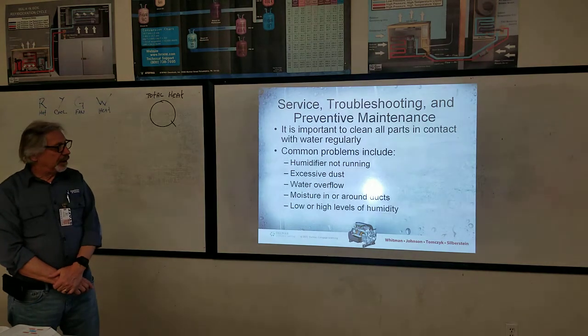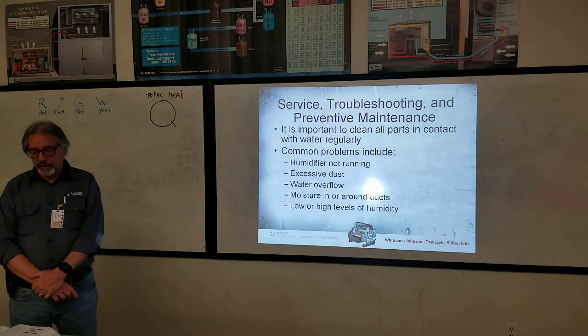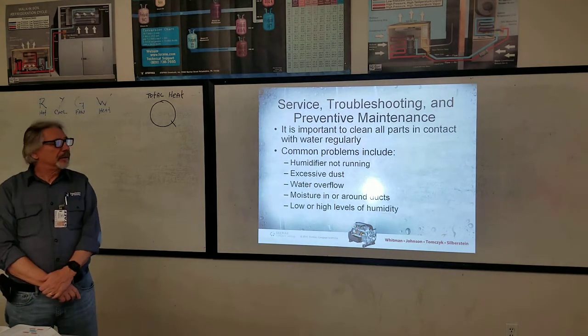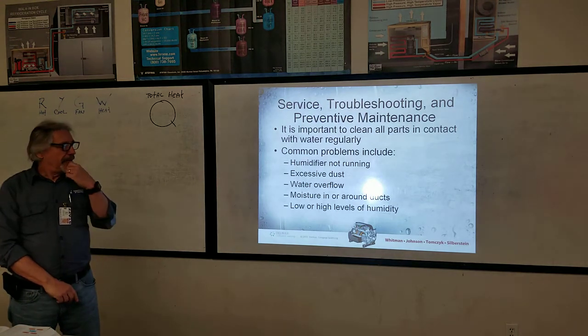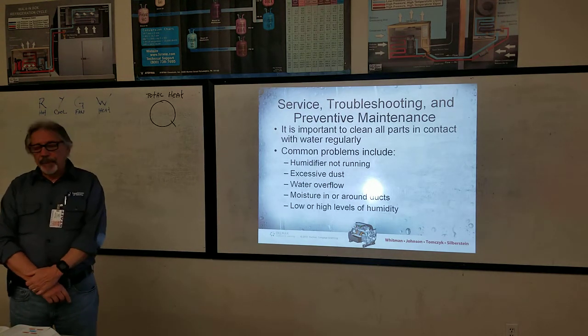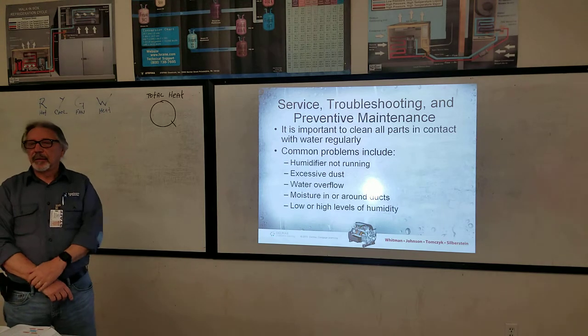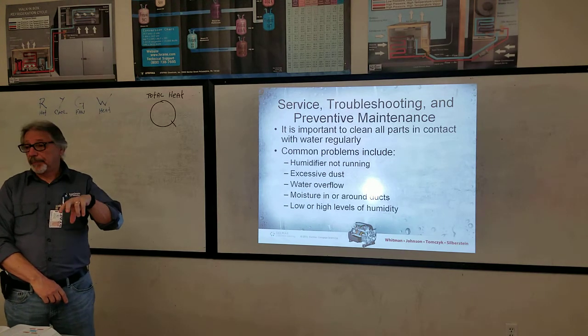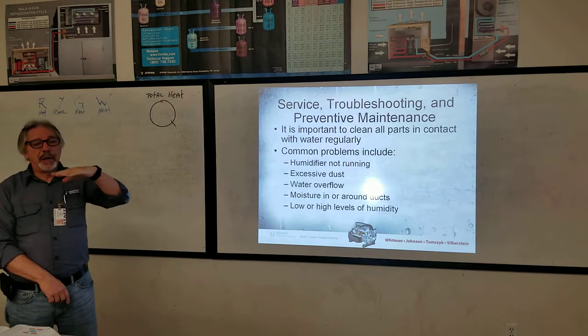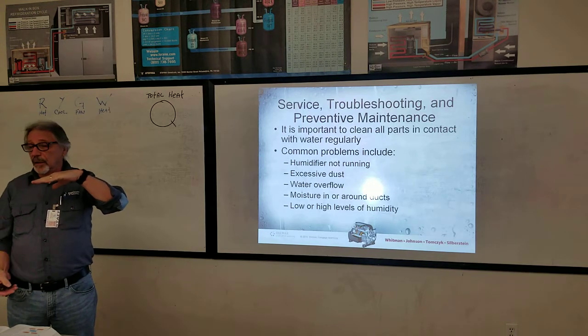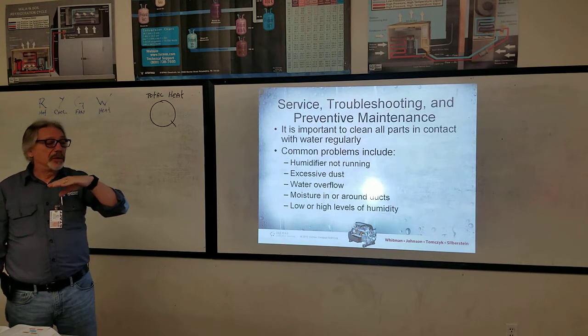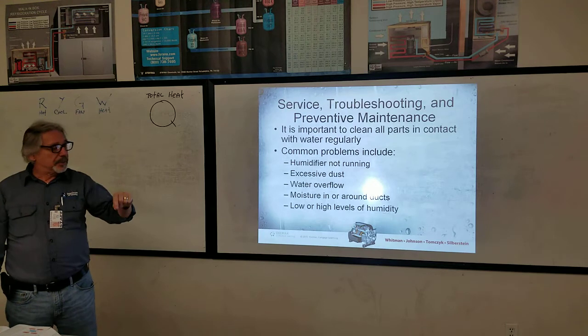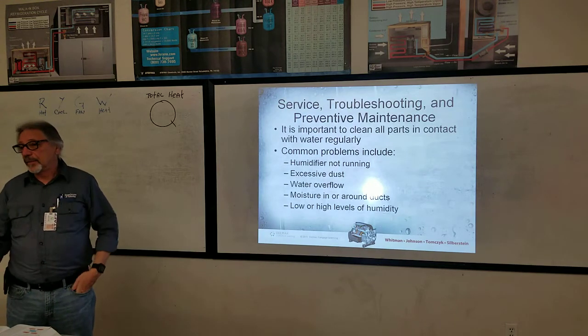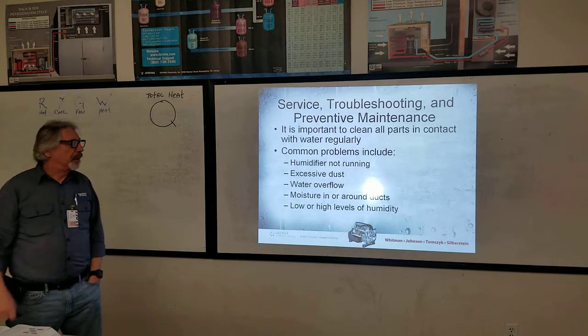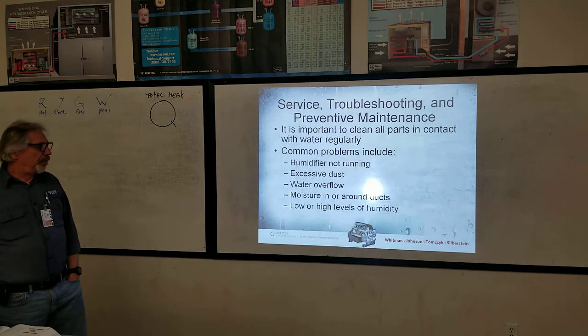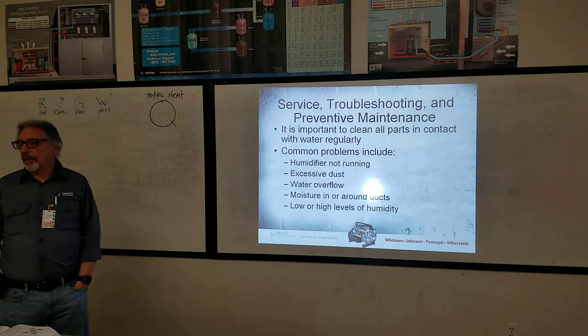So the humidifier was having problems one day, so I had to go out there. What happened is the drain got plugged up, and the water level got so high that it shut everything off as far as the humidifier goes. That's what happens when the drain gets plugged - it's a safety feature that shuts everything off. Once I blew out the drain, everything worked fine.